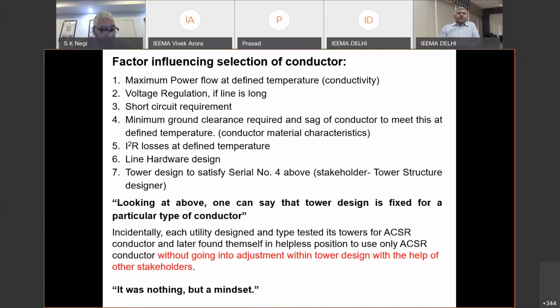And that's why the limitations of the ACSR Moose conductor did not allow us to flow more power in the transmission system. And now, why could this tradition of ACSR Moose usage not be overruled? Mainly it was due to the utility, due to lack of collaboration, I will say, between the stakeholders.